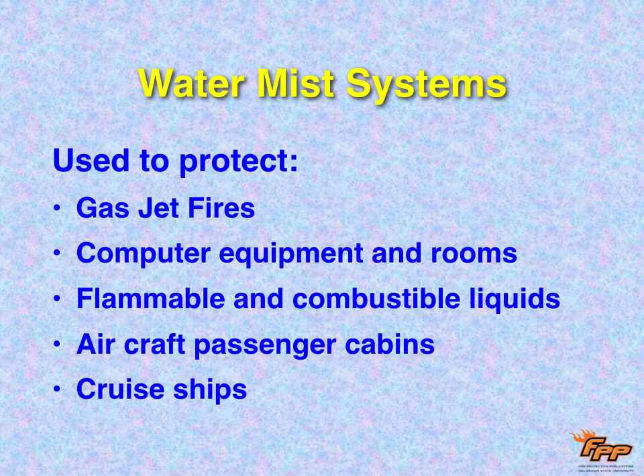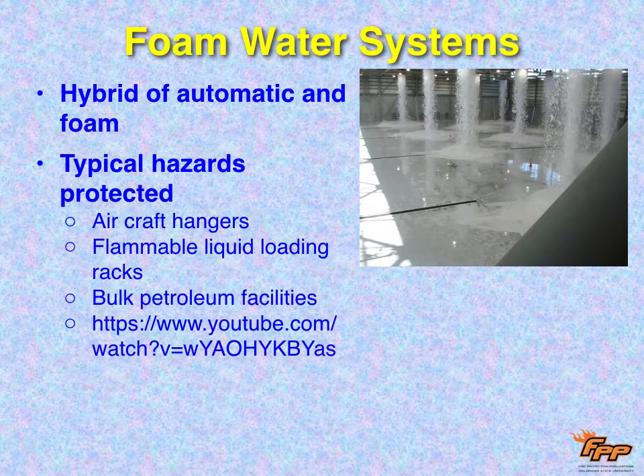Flammable, combustible liquids. Where you do see them sometimes is aircraft passenger cabins and cruise ships. And the military uses these in a lot of their ships. And then, as I mentioned before, we have foam water system, which is water that goes through the plumbing and then mixes with Class A foam or Class B foam. Usually it's going to be Class B because these are used for hazardous materials and flammable liquids. You can see them in aircraft hangars, bulk petroleum facilities, flammable liquid loading racks.